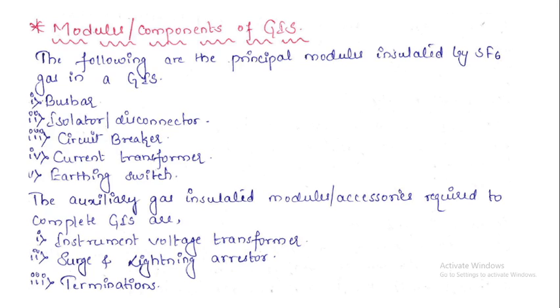Then moving on to the modules or the different components of the GIS system. What are the different components these gas insulated substations may contain? The following are the principal modules insulated by SF6 gas in a GIS: bus bar, isolator or the disconnector, circuit breaker, current transformer, earthing switch. So these are the 5 different components we have. Apart from this, there are auxiliary gas insulation modules or accessories required to complete the GIS: instrument voltage transformer, surge and lightning arresters and the terminations. So these are the different auxiliary equipments we do require.